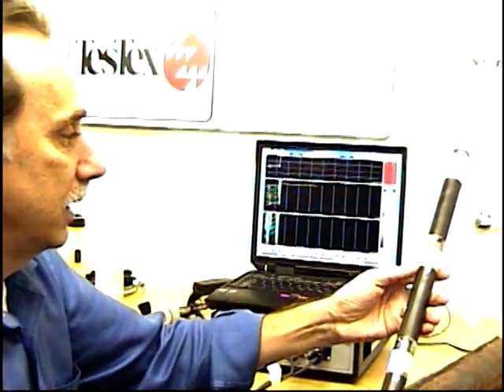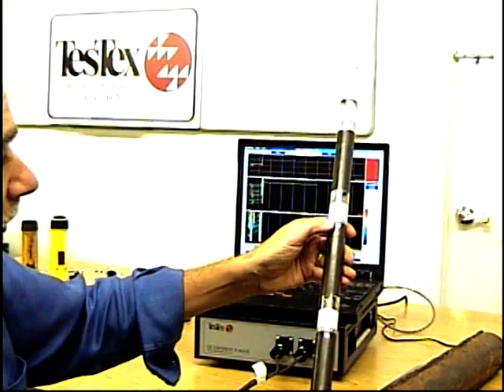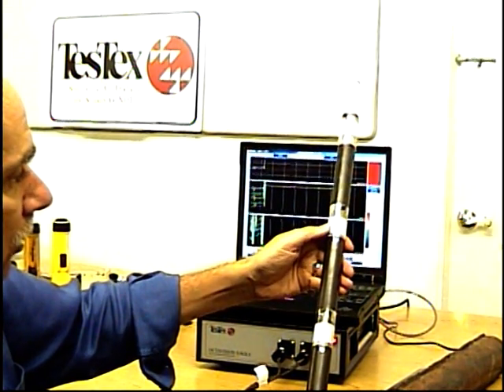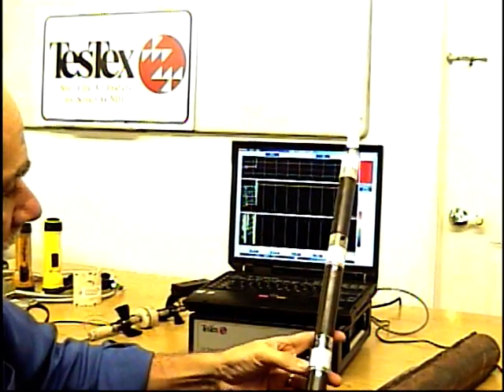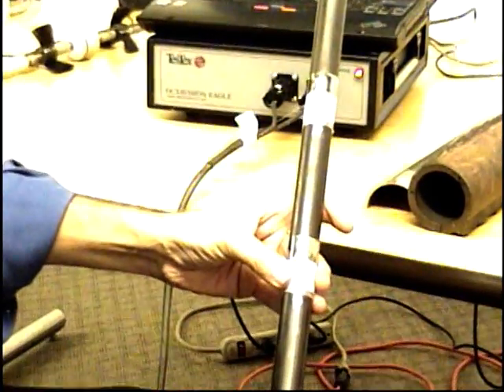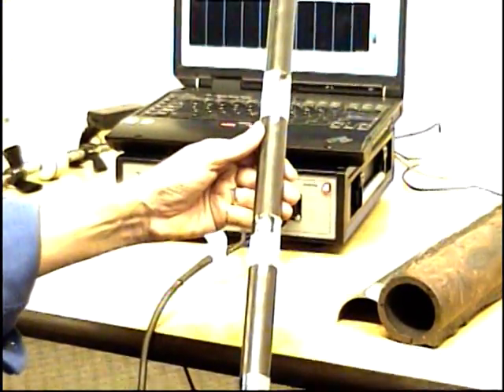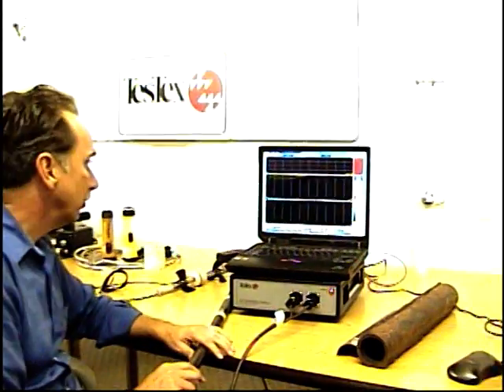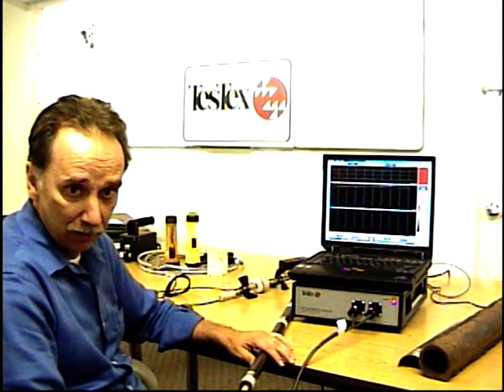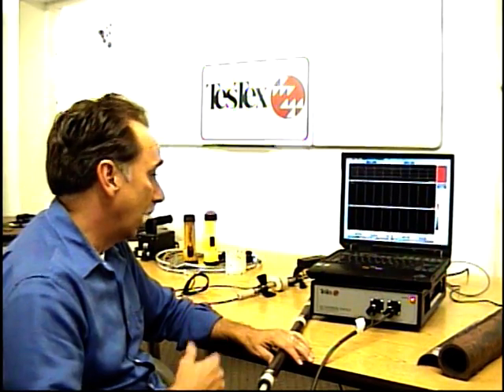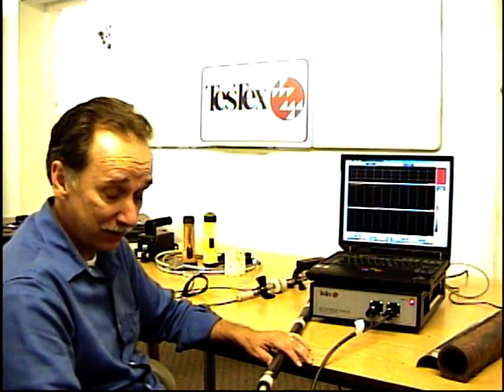Before I do that, if you look closely, I don't know how well it's going to show up, but we got 3 different size pits. We have a 92% pit, 76, and a 58% pit. These are 1/4 inch diameter. Keep in mind, probably when somebody asks you what's the lowest or smallest pit you can find, typically we say 1/8 inch pit, 30% deep. In the labs, we've actually seen smaller, as small as a 16th inch pit.